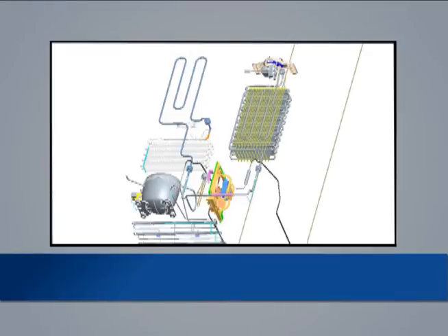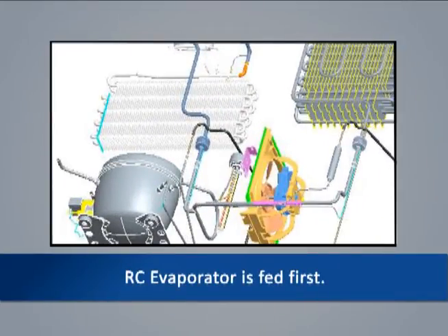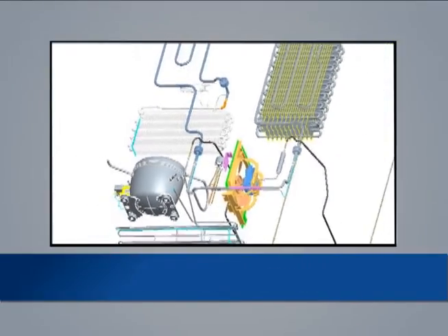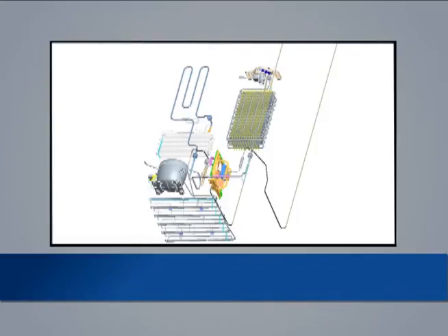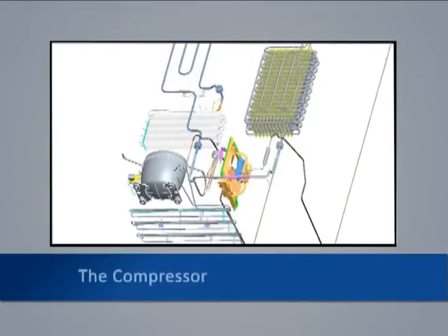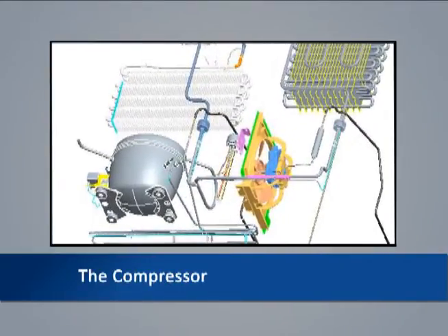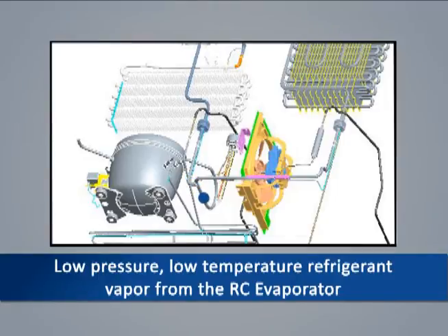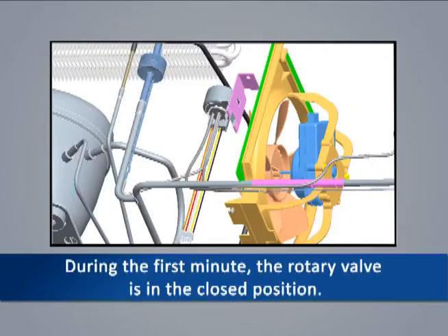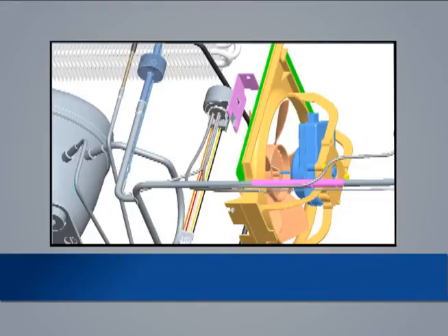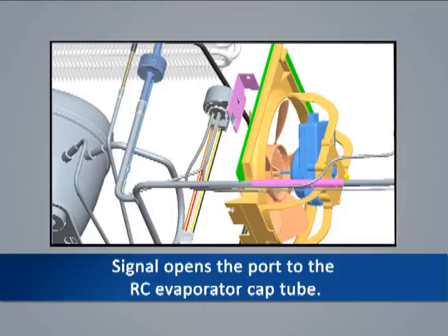On an initial start-up of a dual evaporator system, the RC evaporator is fed first. After that, the control supplies refrigerant to the evaporator most in need of cooling. Assume a refrigerator has been operating normally and the board has determined the RC compartment requires cooling. Starting at the heart of the refrigeration system, the compressor and condenser fans are energized by the control board. The compressor pulls low pressure, low temperature refrigerant vapor through the suction line from the RC evaporator. The vapor is compressed to a high pressure, high temperature vapor and exits the compressor through the discharge line to the condenser. During the first minute of compressor operation, the rotary valve is in the closed position. One minute later, the control board sends a signal to the rotary valve, which opens the port to the RC evaporator cap tube.